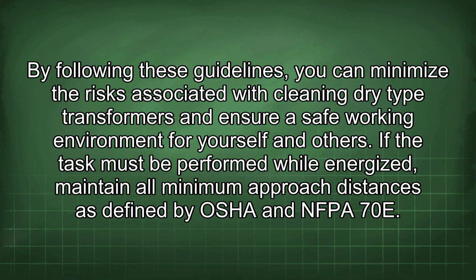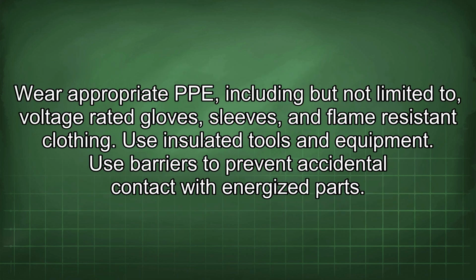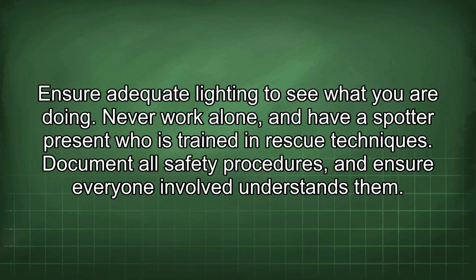for yourself and others. If the task must be performed while energized, maintain all minimum approach distances as defined by OSHA and NFPA 70E. Wear appropriate PPE, including but not limited to voltage-rated gloves, sleeves, and flame-resistant clothing. Use insulated tools and equipment. Use barriers to prevent accidental contact with energized parts. Ensure adequate lighting to see what you are doing. Never work alone and have a spotter present who is trained in rescue techniques. Document all safety procedures and ensure everyone involved understands them.